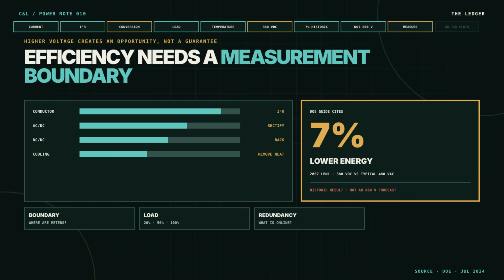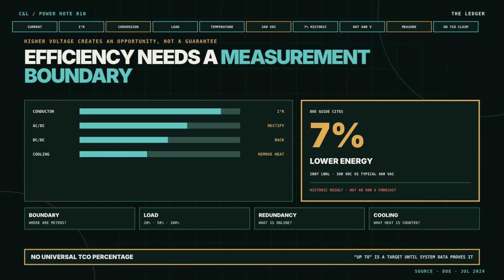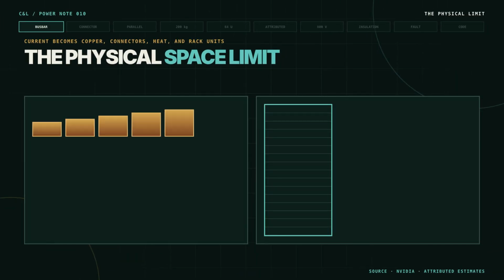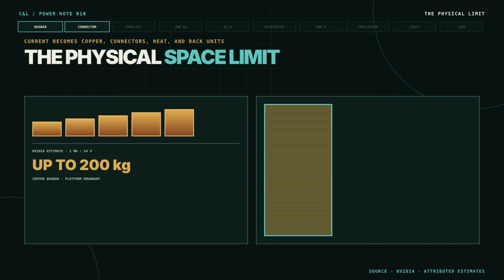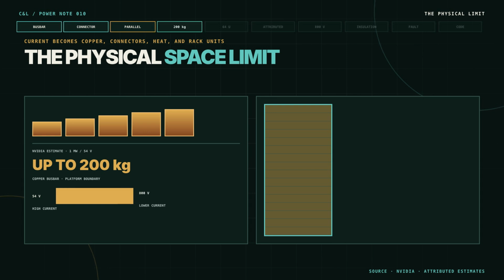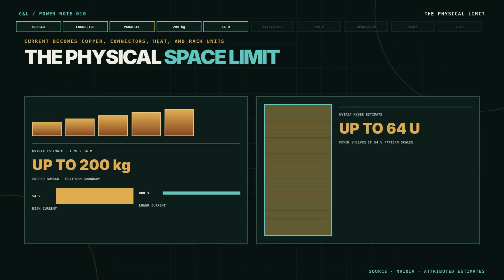A credible comparison must state the measurement boundary, loading range, redundancy, and cooling treatment. Vendor "up to" percentages are design targets, not universal operating cost promises. The physical prize is current capacity per unit of rack and conductor. NVIDIA estimates that a 1 megawatt rack on a 54-volt bus could require up to 200 kilograms of copper busbar. It also says power shelves could occupy up to 64 rack units in its future Kyber configuration, leaving no room for compute. Those are platform-specific NVIDIA estimates, not universal rules, but they expose the constraint.